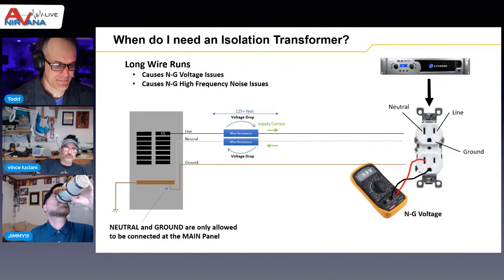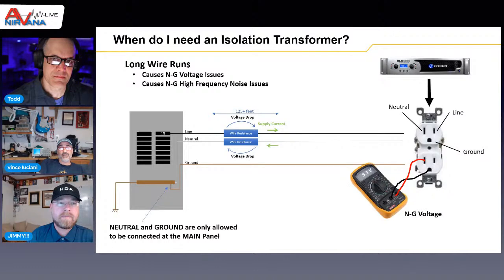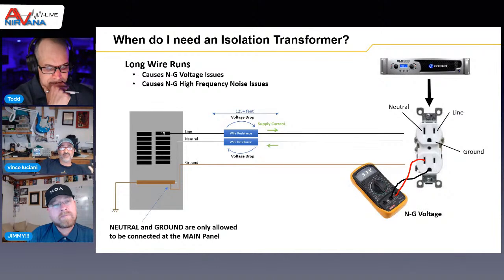Not only will you get a voltage drop, but when I measure the voltage between neutral and ground, I'll actually get a voltage there. That is not advantageous to a lot of sensitive electronics. That neutral-to-ground voltage is responsible for noise, which manifests itself as equipment getting locked up, or as audible noise in a reference audio system.